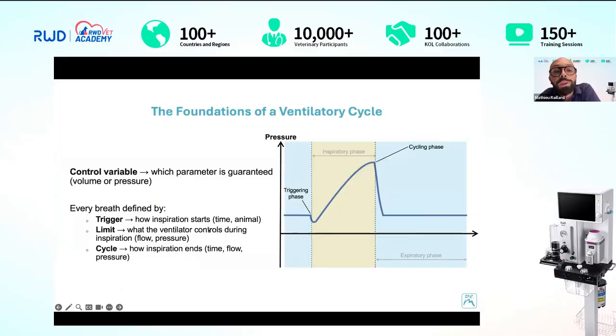Moving on. When we look at the ventilatory cycle, I have decided that I need to ventilate an animal and that I'm going to use an automatic ventilator. When I look at the ventilatory cycle done by a ventilator, there are 4 things to consider. The first point is the control variable. Which parameter do I want to guarantee? I have 2 options there. I can decide that I want a given pressure throughout the inspiration, or I can decide that I want a given volume in the lungs at the end of the inspiration.